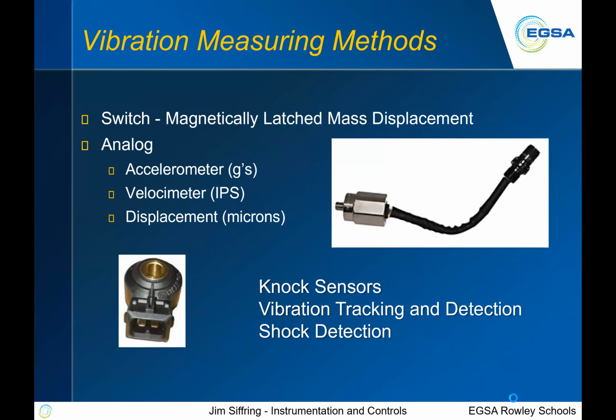All right, let's talk about vibration measurement. A couple of different things you can look at. One being just a basic switch, as in a magnetically latched mass displacement device, and I'll show you one of those as we come through. Effectively, a device that's held together by a magnet, and if you hit it too hard, it breaks the connection with the magnet and opens up. Or you've got analog type signals that'll give you some sort of signal out: accelerometers, velocimeters, displacement devices. So what do they use them for? They use them for knock sensors, vibration tracking, shock detection.